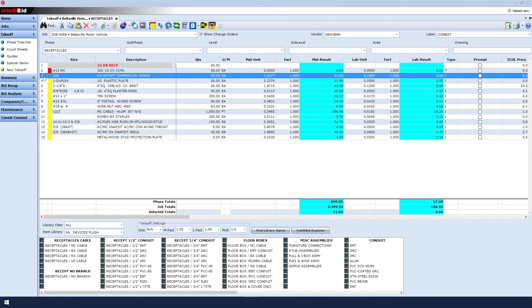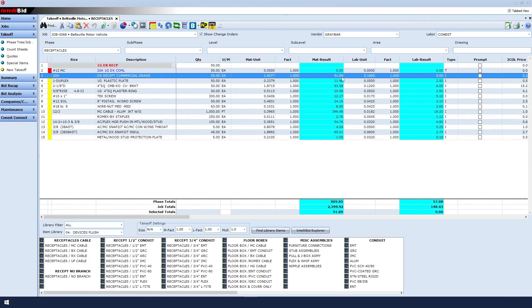So then Line 3 is the actual device. That's the commercial grade duplex receptacle with a quantity of 50. The price is $1.83, and that number times 50 equals $91.89. I have a labor unit of 0.18 times 50, which equals 9 labor hours.